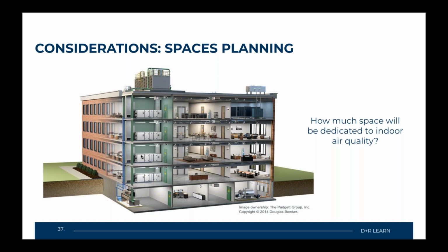What you're going to find is that you can save a lot of space in a facility this big by utilizing, instead of a hydronic system with cooling towers, chillers, and air handler units, a VRF system which pipes directly into each office space using a cassette type or even a wall-mounted indoor unit. All these mechanical room spaces can now be converted into nice real estate for other uses. So in your planning phase, whether fresh construction or renovation and upgrades, you want to consider how much real estate is available for that specific system.